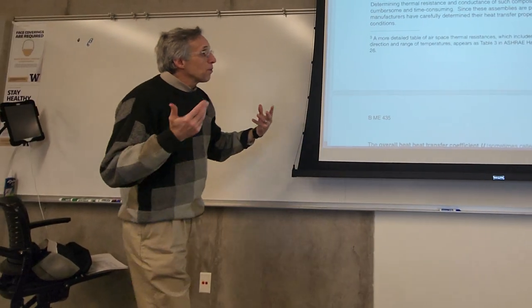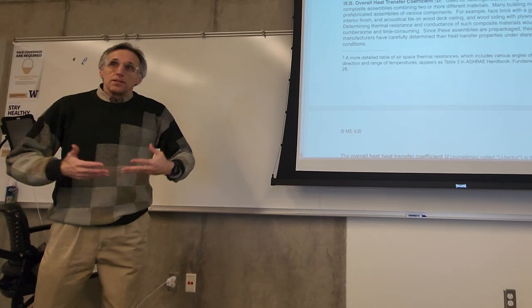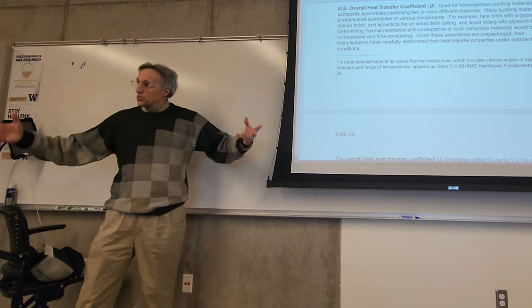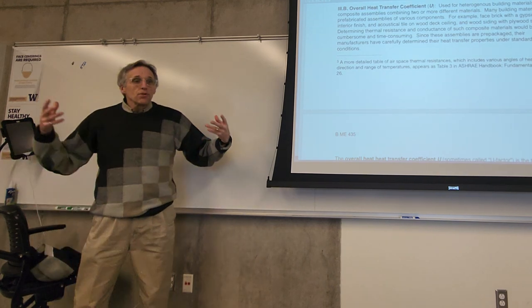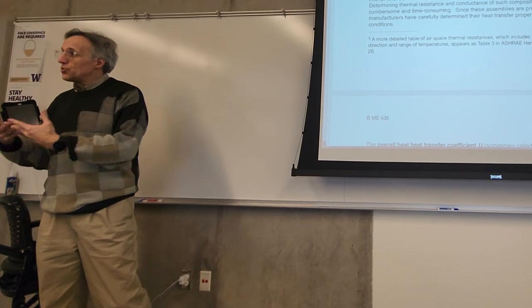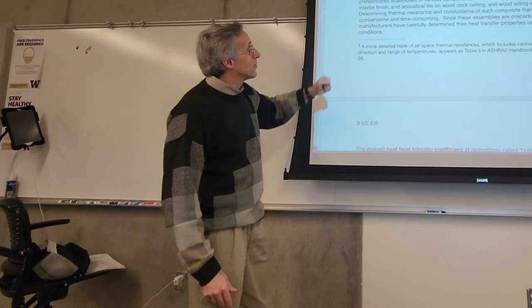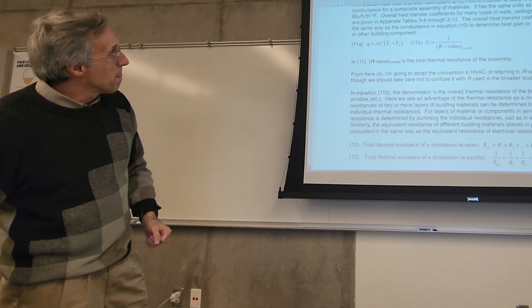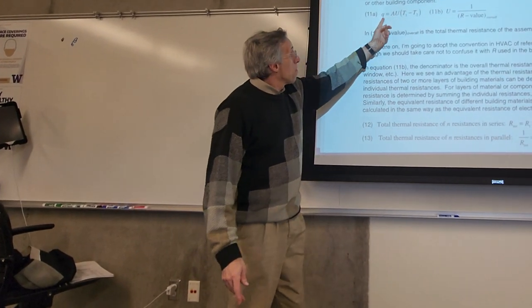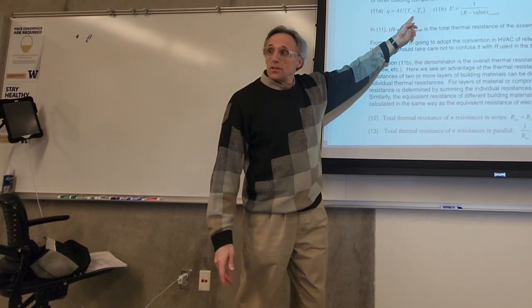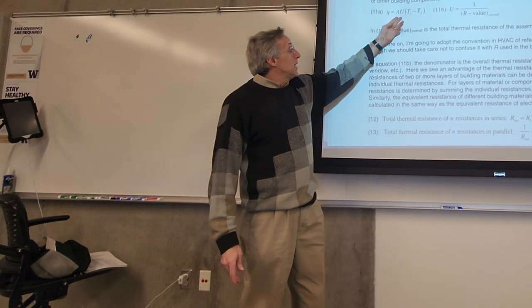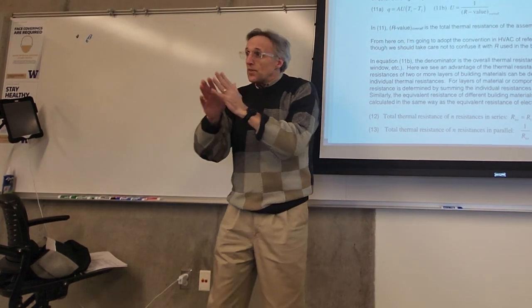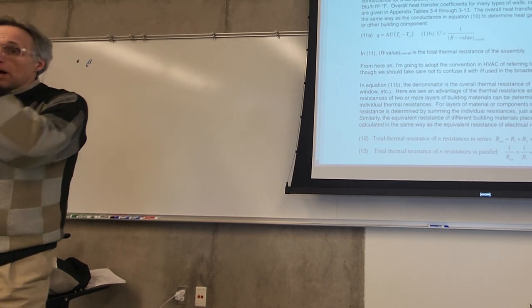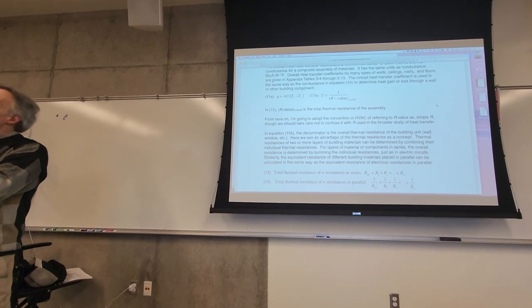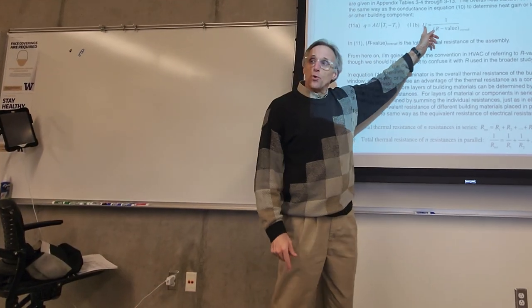And so generally when we're doing a load analysis, we need to get all of our R values, and sometimes C values if it's conductance, and convert them into U values. And then we use U values in our calculation for the heat transfer. And then our heat transfer would be Q equals area times U times delta T. And the nice thing about the resistivity is the R values add. So if you have components in series, you add up their R values, you get a total R. Then you flip the R. You flip the R to get U.